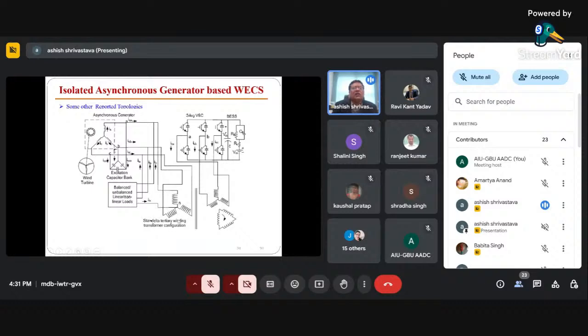Then you have a star delta tertiary winding. Once we are talking about an isolated transformer, it is an integral part, creating isolation. Voltage is being injected using the turns ratio being maintained here. This is a tertiary, you can say dummy, delta connected three-phase winding. Star connected is also there on both sides. So this is the star delta tertiary winding transformer configuration.